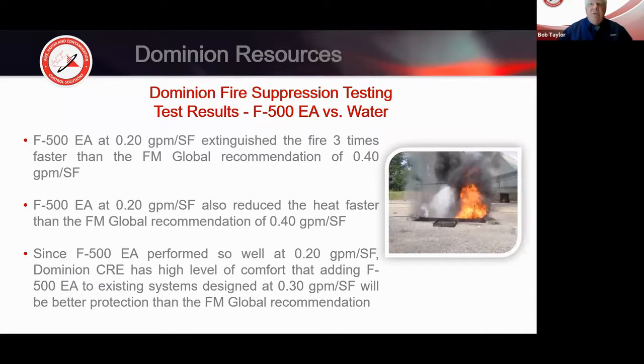Just some work that was done with Dominion Resources. One of the Dominion results that they identified, and again, they provided some background, is that typically the recommendation by many has been 0.40 GPM over a square foot. Density, we've actually found that with F500, or they should say they proved, as well as others, that 0.20 is much faster and better, and that's what's really needed. So you're using less liquid, less runoff, less everything, but more efficient than other types of agents, including water. So it does really highlight the merits of using that.